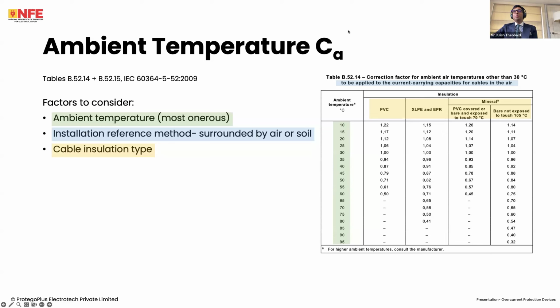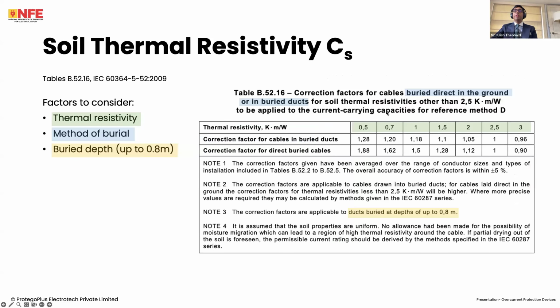The installation reference method, so cables in air in this case, the insulation type PVC, XLPE, mineral insulated, and so forth. Soil thermal resistivity, if the cable is buried within the ground, the ability of the soil to dissipate heat matters a lot. The thermal resistivity of soil, obviously, in kelvin meters per watt. The method of burial, so in this case, it's a buried duct or it is buried in the ground. The buried depth, of course, if it's in a duct, these factors only apply to 0.8 meters. Further allowances are made if it's beyond 0.8 meters.